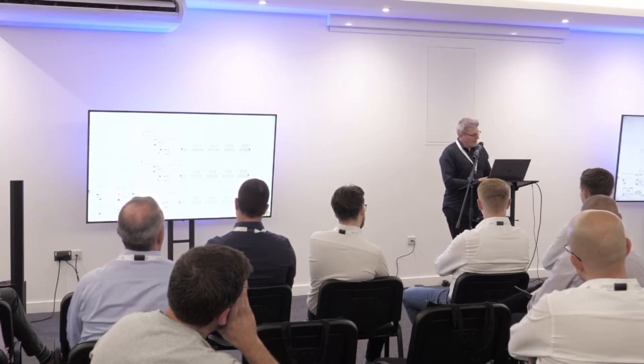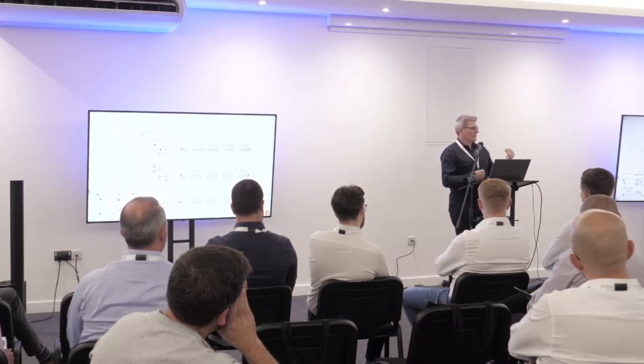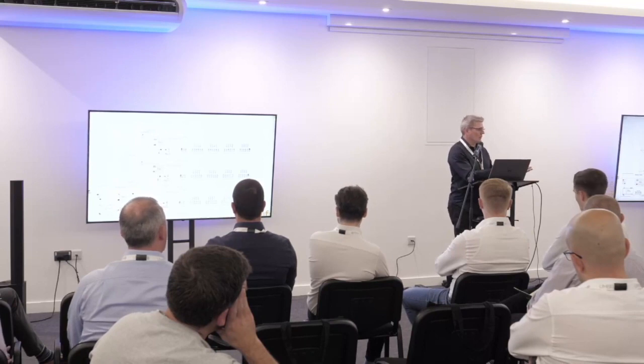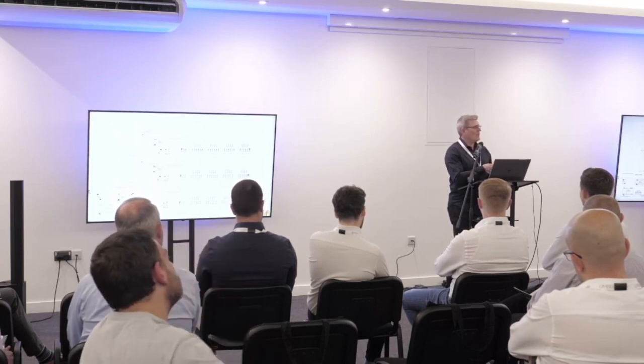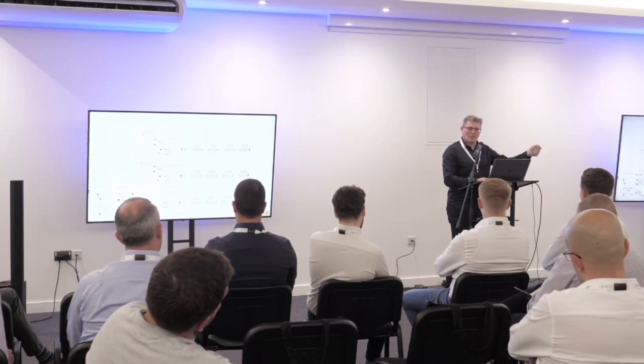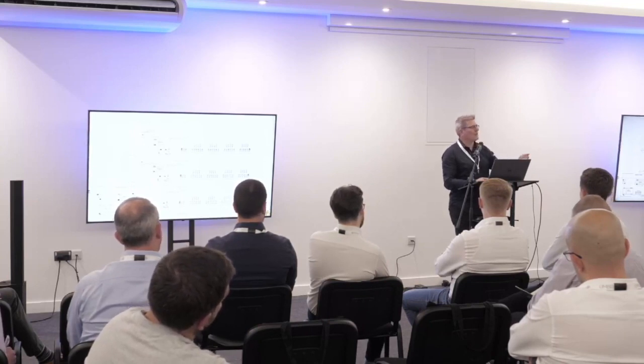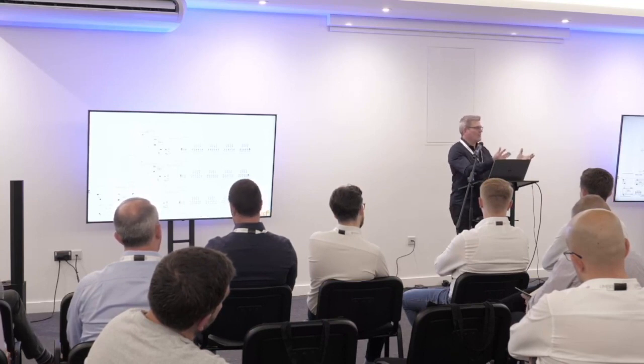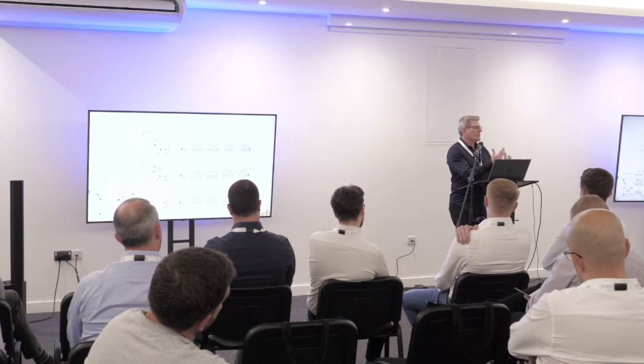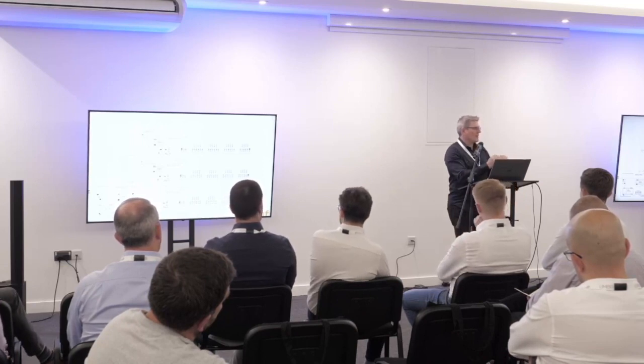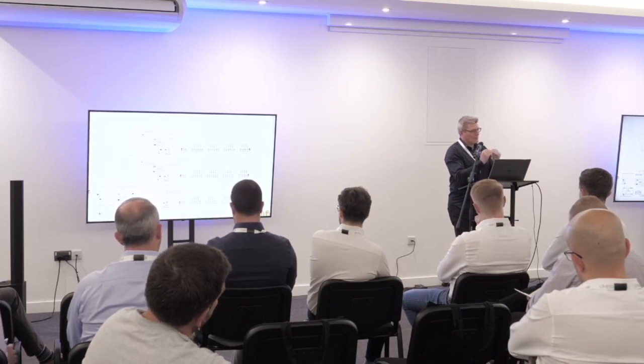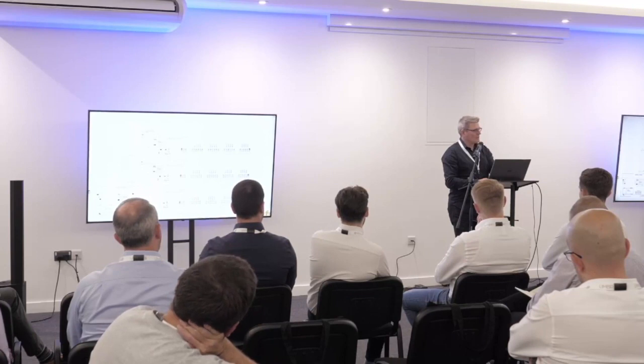The next level down tends to be network, because we're dependent on these large installations, and even in a high-end residential or small commercial environment, you inevitably have devices connected together over IP. They're connected to switches. If the network goes down, or somebody unplugs a cable from a patch panel, or the network guys reconfigure a switch and suddenly your device isn't on its VLAN anymore, that's the next level down, where the network is causing a comms issue. I can genuinely say that when it comes to KNX devices on the KNX bus, they are really robust.